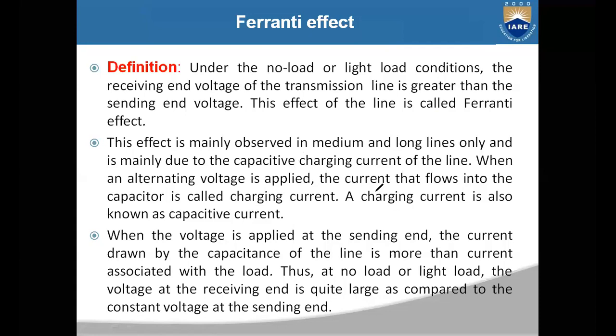When voltage is applied, the current drawn by the capacitance of the line is more when compared to the load. Under light load conditions, if it is a long transmission line and you apply sending end voltage VS, there is no load or only a light load. In such a case, the current flowing through the capacitance will be very high compared to the load current. So because of that, under no load, the receiving end voltage will be greater than the sending end voltage. This effect is called the Ferranti effect.